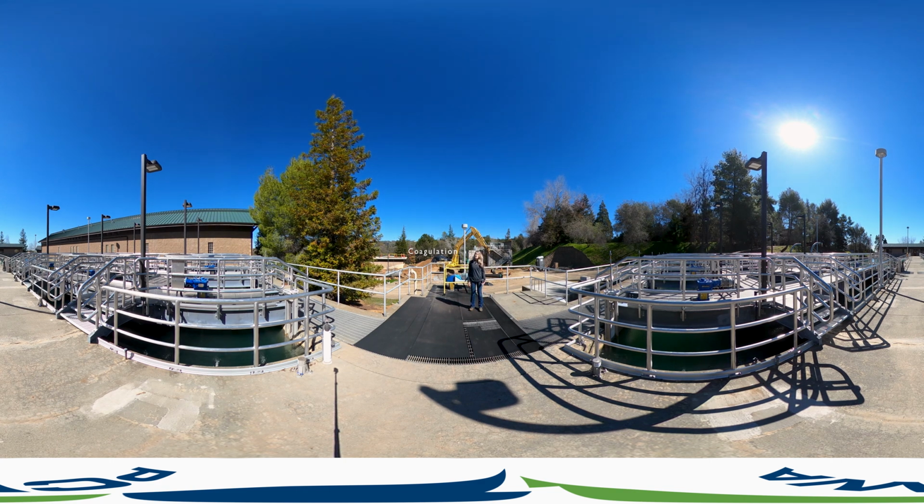A positive charge from our coagulant neutralizes the negative charge of the dissolved and suspended particles in the raw water, and they attract each other like a magnet. Those particles are able to bind and form larger particles that we can settle out in this process. From here, it splits into two parallel flocculation sedimentation basin trains, and I'm going to walk you through these next steps.